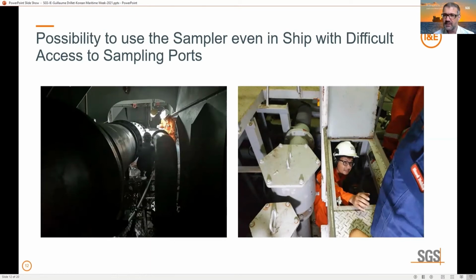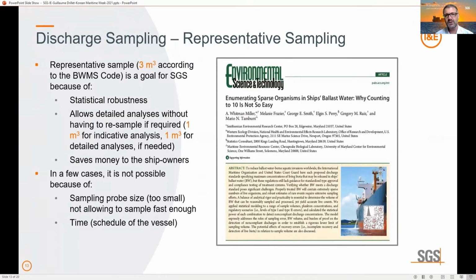It can be a little challenging from the testing side as well. We talk about volume, 3 cubic meters in the code, 1 cubic meter for each analysis under the commissioning test, meaning at least 2 cubic meters if you do detailed analysis. The nice paper from Miller et al. in 2011...